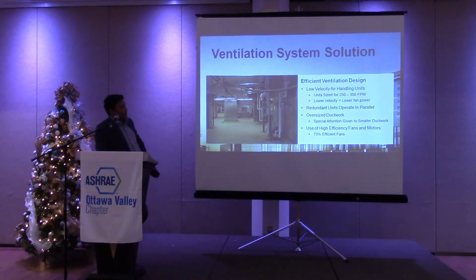Now, I will say that one of the challenges for the project was when you say, okay, I'm going to oversize air handling units, you're paying more money for bigger air handlers. And so that's quite a premium there. Floor-to-floor height is a big deal. You need high floor-to-floor heights in your mechanical room because you've got bigger ductwork, bigger units. You need high floor-to-floor heights on the individual floors when you're doing distribution.